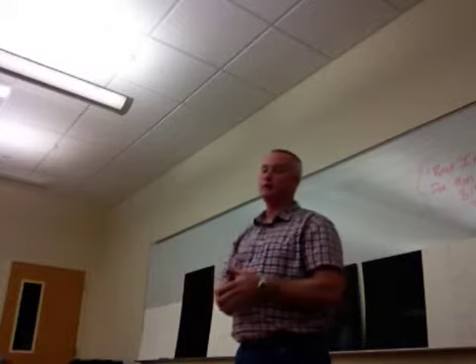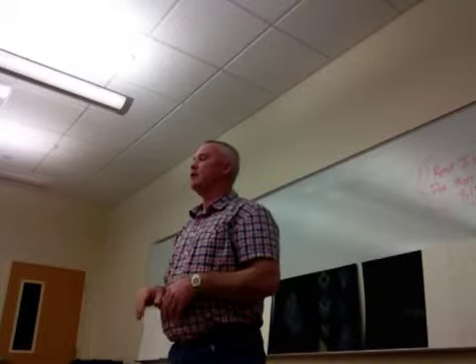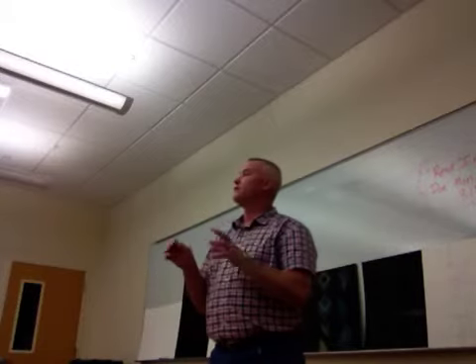There are programs that you can feed parameters in, feed IES files into for a certain fixture at a certain mounting height with certain reflectance on the walls, the ceiling, and the floor, that for a given number of fixtures of a given type, you can get 35-foot candles right here, 3 feet off the floor. Or you can make them more dense and brighten them up a little bit, get 50-foot candles here.